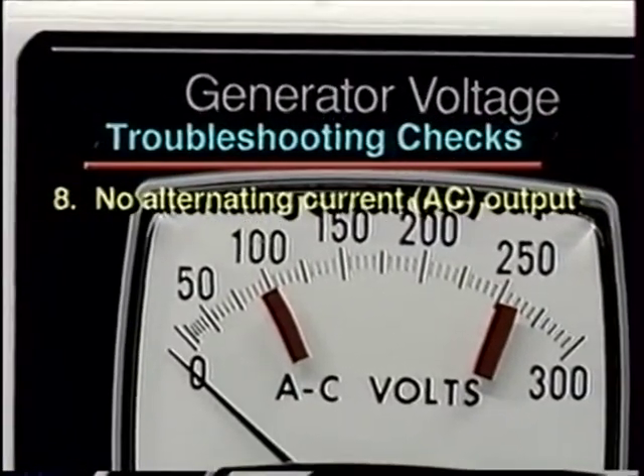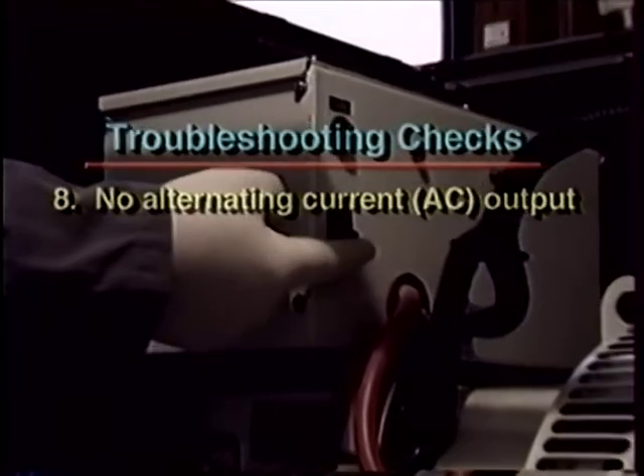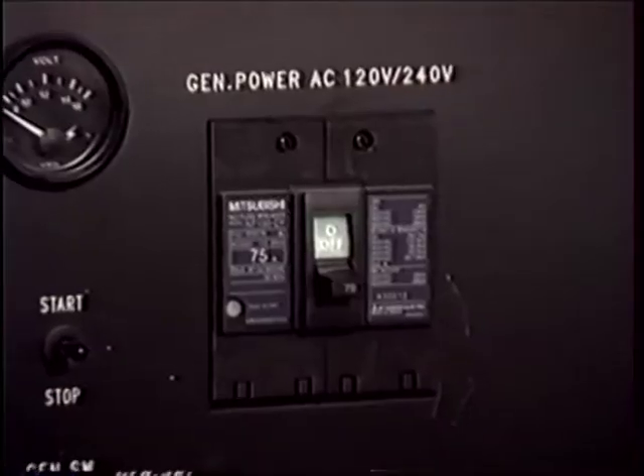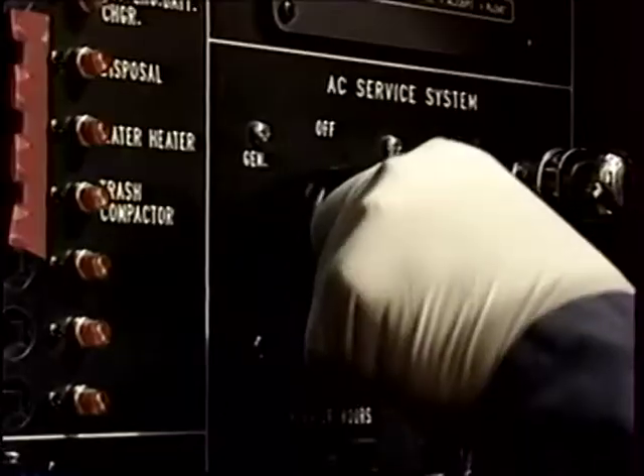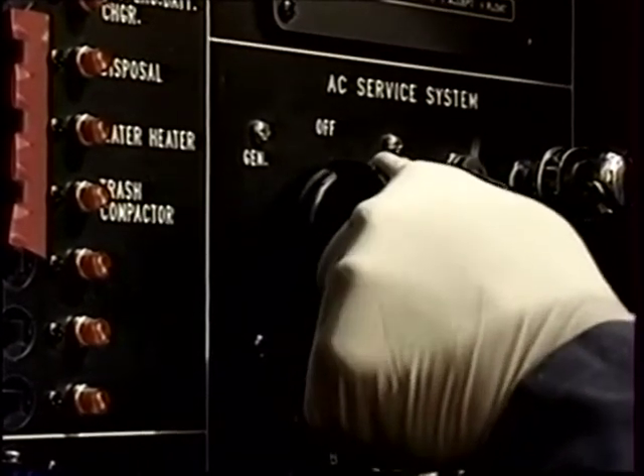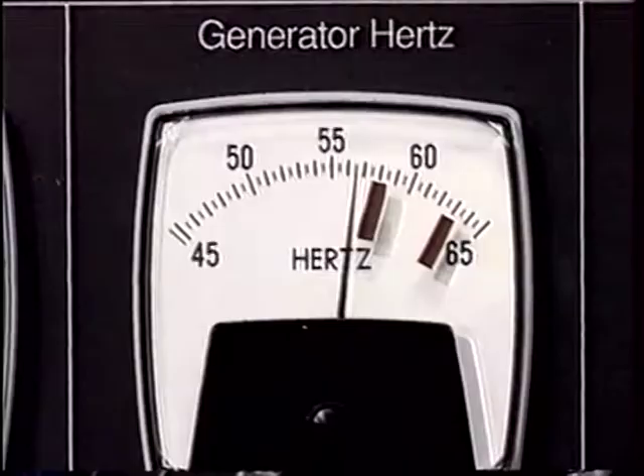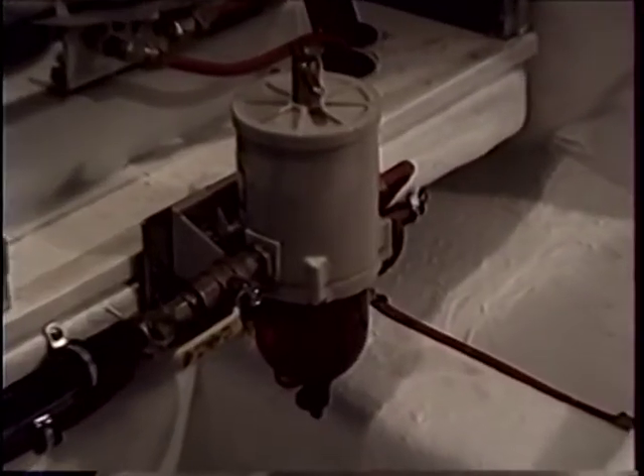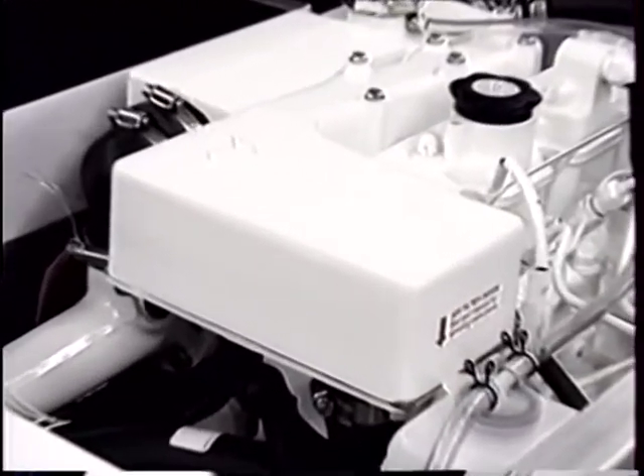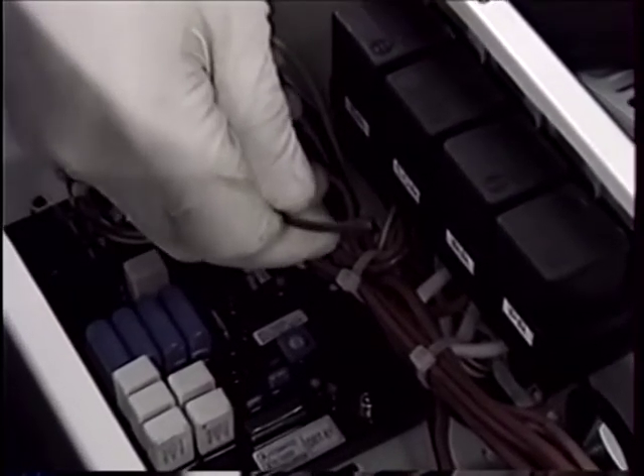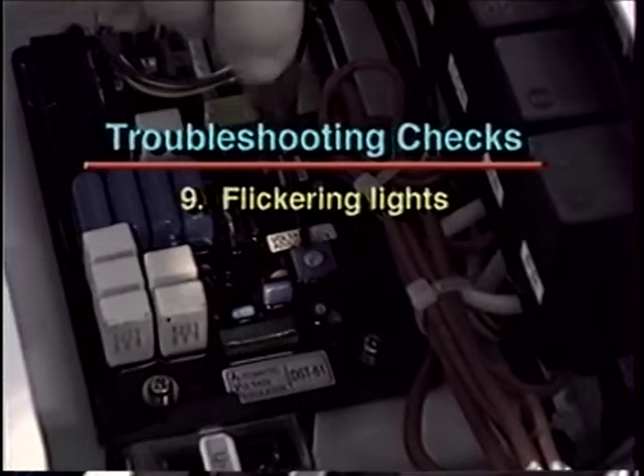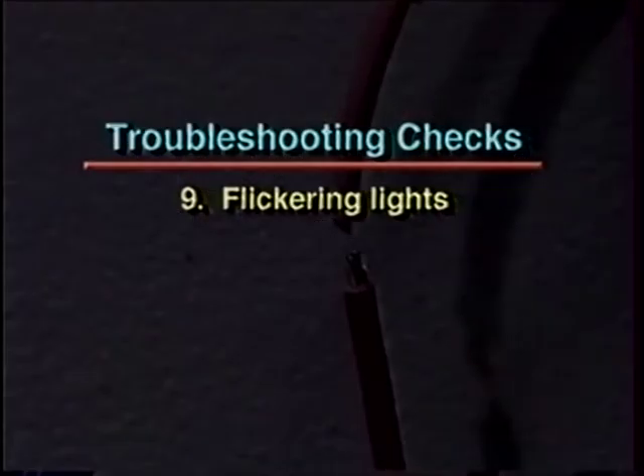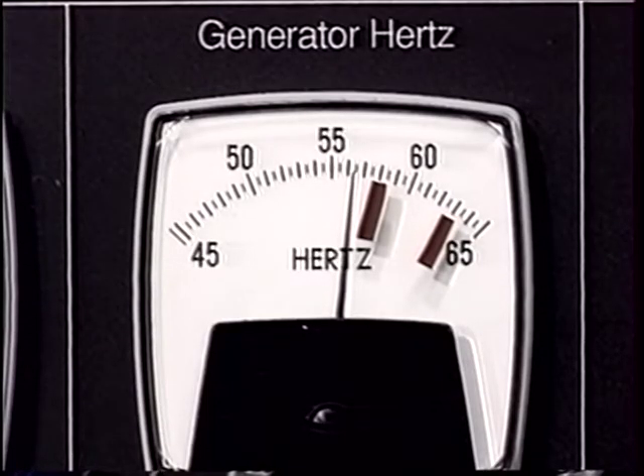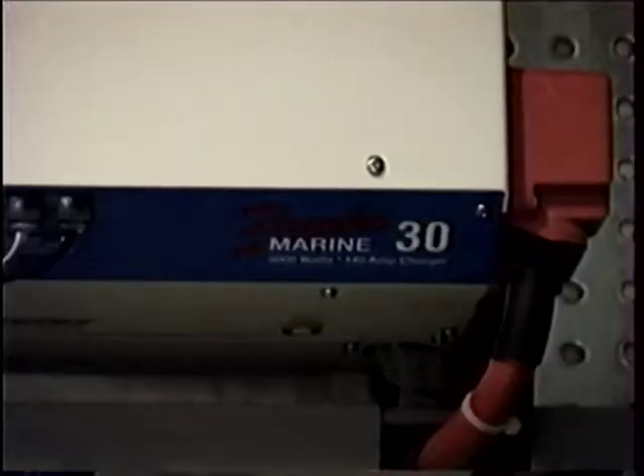Common generator end problems include no AC output, which can be caused by an open field circuit breaker on the generator junction box, an open mainline circuit breaker, a faulty generator selector switch, the engine speed running too slow because of restricted fuel, a blocked air system, or a broken wire in the generator junction box. Flickering lights can be caused by a faulty setting on the AC voltage regulator, an intermittent electrical short somewhere in the vessel, the engine speed running too slow, or load switching off and on.